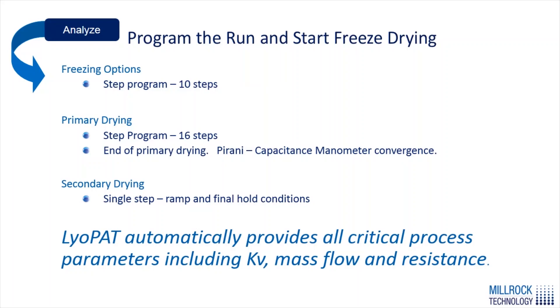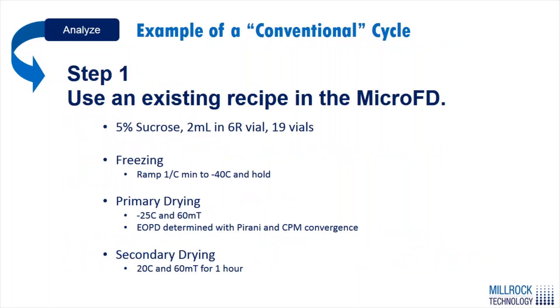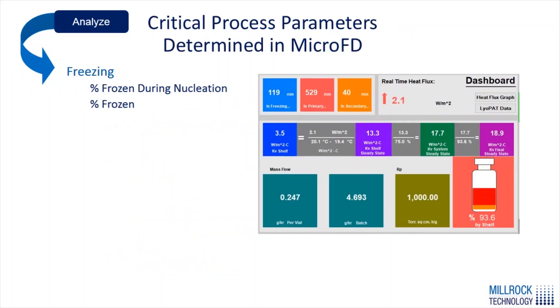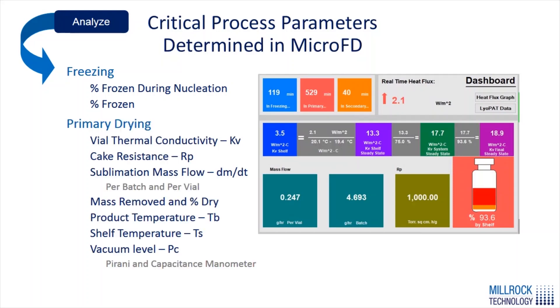To start, we ran a plain recipe-based freezing program where we just ramped to a steady temperature in freezing and primary drying. During this cycle, LyoPAT automatically calculated all critical process parameters throughout the run, including our Kv, mass flow, and cake resistance. The specific recipe used was ramping at 1°C per minute to minus 40, then drying at minus 25°C at 60 mTorr. The product was 5% sucrose, 2 milliliters in a 6R vial, with 19 vials used in the array.